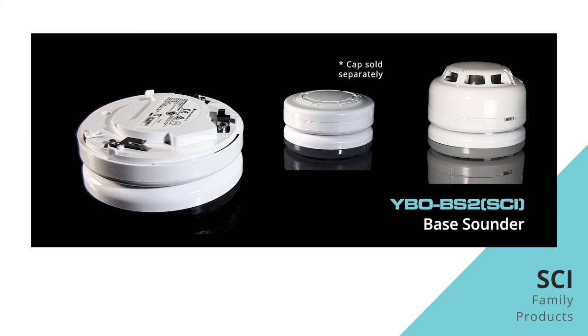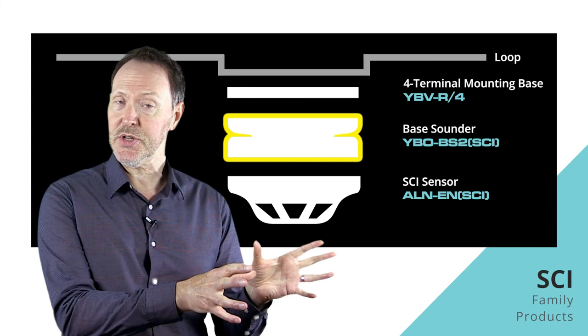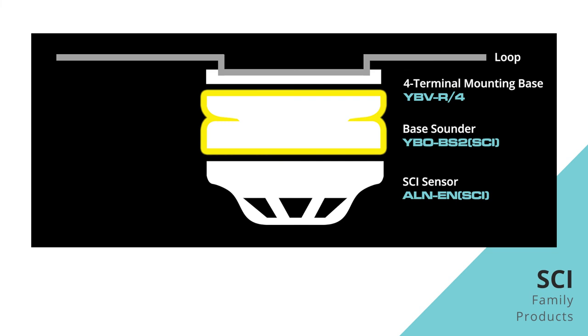In case you were wondering what would happen if you fitted one of our SCI sensors onto one of our SCI base sounders, well, as it's the base sounder that's physically connected to the loop cables, in this instance the SCI functionality is active in that device, not the attached sensor, which would just perform as a standard sensor here.